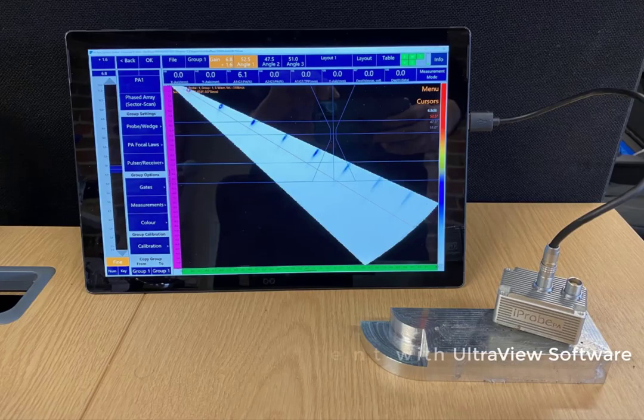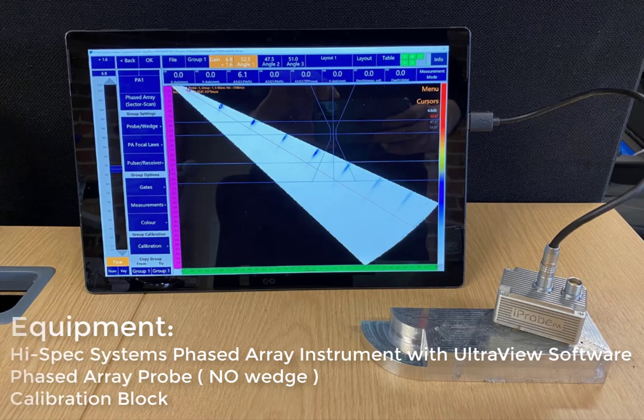The equipment needed for this calibration is a Hi-Spec Systems phased array instrument with UltraView software installed, a phased array probe without the wedge connected, and a calibration block. We will be using the iProbe phased array system for this calibration.